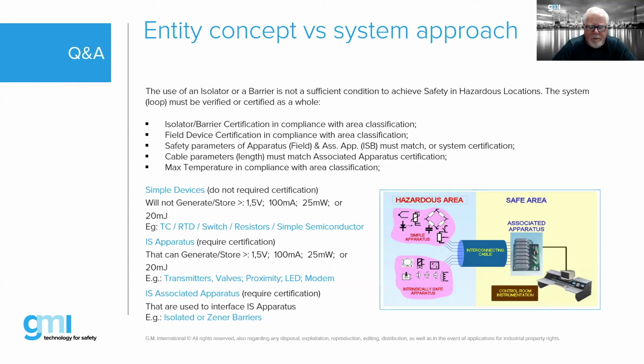I'll give you an example. We did a project with a client not too terribly long ago, and based upon the gas group, this happened to be a 2C gas, which included hydrogen. So it was one of the most onerous applications, and hydrogen has a very low ignition energy. So basically, the amount of capacitance is limited. It's very, very small. Therefore, the cable length had to be extremely short. What we actually found was that for about 90% of their runs, the cable length was fine. But in about 10% of their cable runs, they exceeded the maximum parameters allowed for the cable. So the solution was to move the barriers closer to the devices in the field to shorten that length.